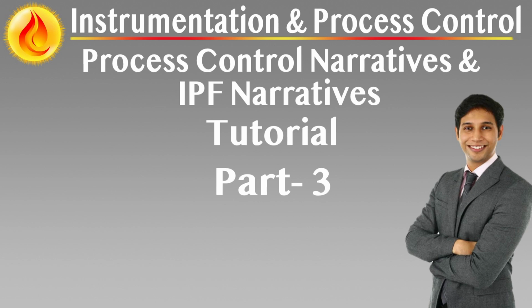Scope and applicability. The functionality overview narrative is required when controller safeguarding logic is spread across two or more subsystems. Typical examples include compressor trains with anti-surge performance and driver control in separate platforms, generator packages with dedicated governor logic, protection relays, and power management systems, rotating equipment monitored by third-party vibration and condition monitoring systems, process skids with embedded PLCs interacting with plant DCS and safety systems.